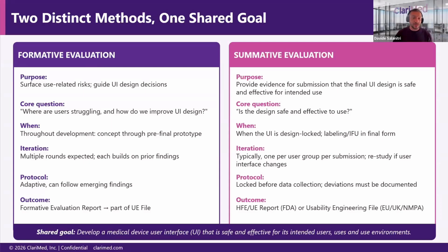Agree. I think, again, agencies want to see that you've done your job. That it's not just do something engineering-wise or design-wise, and then put it in the market at the end. They want to see, did you include the user? Did you identify all the possible risks? Because that's one thing the formatives do. That is, I'm going to introduce the potential users to my device.